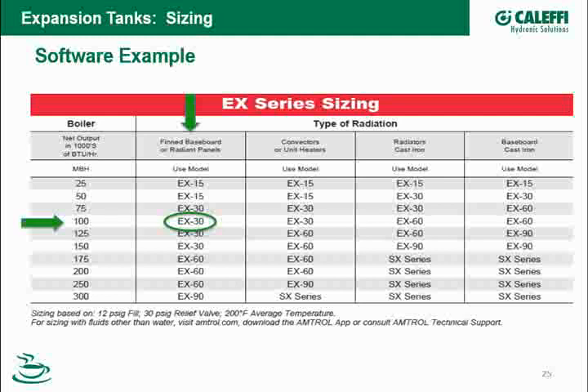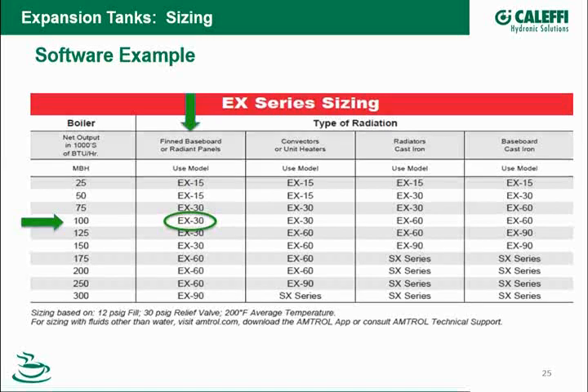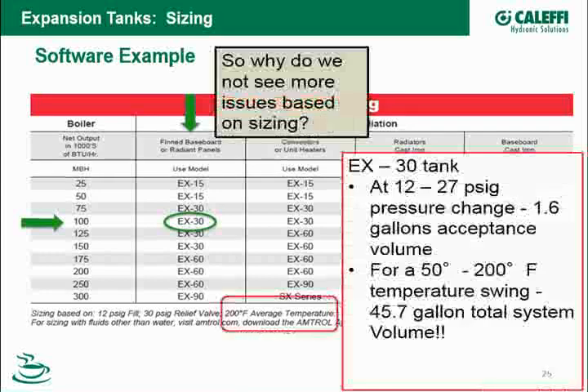It's very conservative. So this kind of chart has been used for a long period of time, and really, you don't see people running into too many expansion tank sizing problems. But they look at that chart and say, well, geez, why aren't there any problems? Well, I'm going to start off with the temperature. For a 200-degree average temperature, you're running your high limit up around 210 degrees to get there. So if I'm running at a lower temperature, there's less expansion, the tank starts to become oversized.